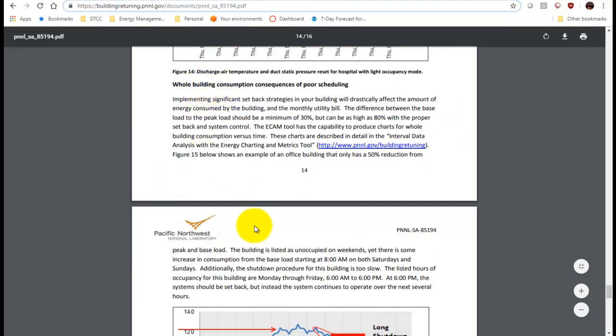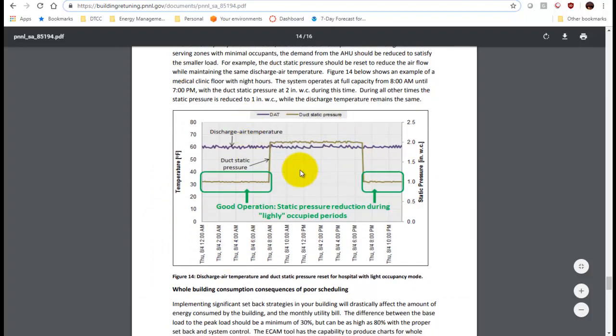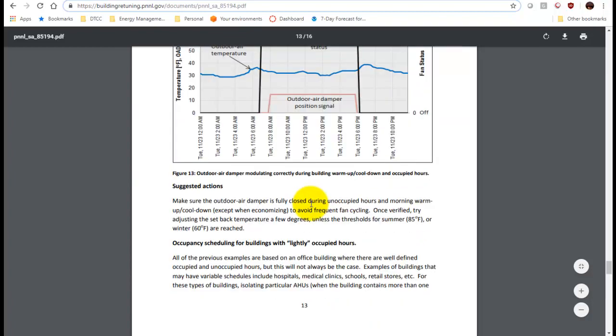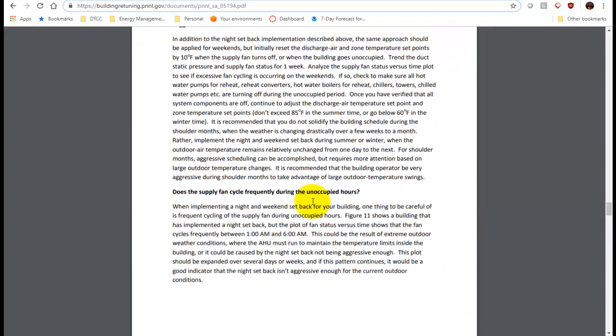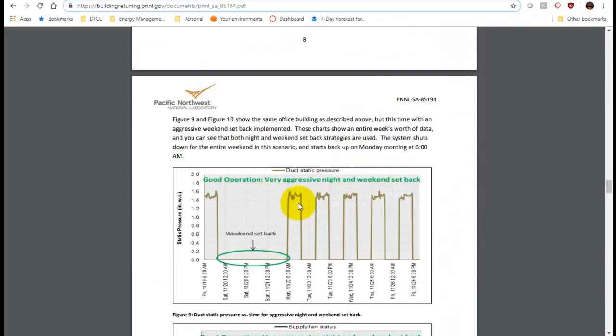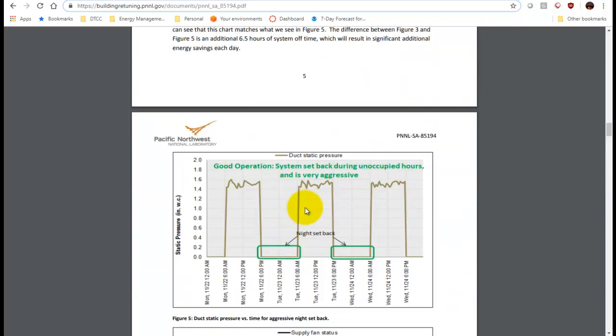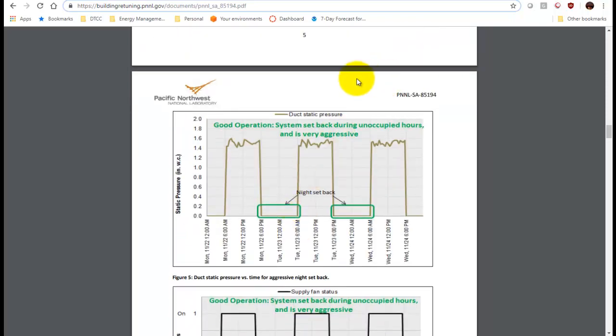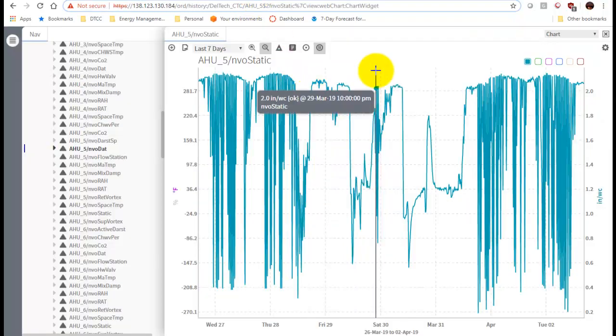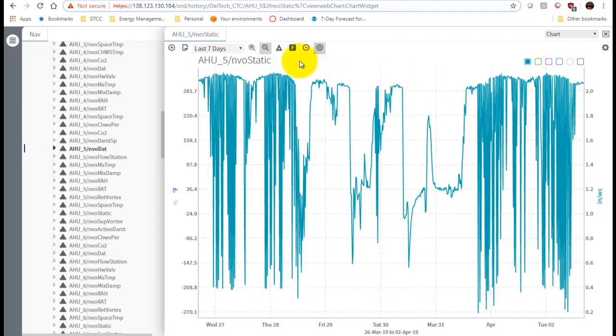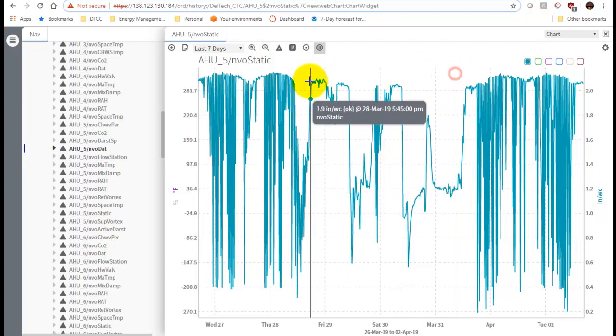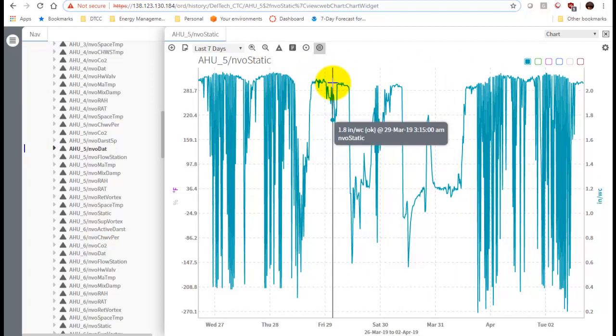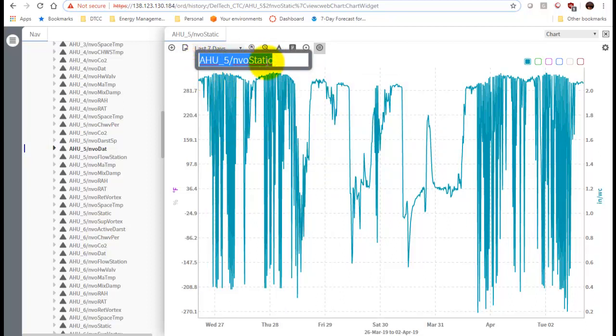The whole idea is you want to try to recreate some of these graphs for each of these areas and then copy, paste, and show whether it's good or bad operation. You don't have to explain everything in the graphs. For occupancy specifically, you just want to go through and talk about whether or not the system has setback. In the case of our AHU it looks like it's not very good. You can export to Excel or as a PDF, but the easiest thing is to just take a screenshot using Print Screen or the Snipping Tool and paste the graph wherever you'd like. You can also change the title to make it easier to read. That's it for this video - that's your retuning overview.